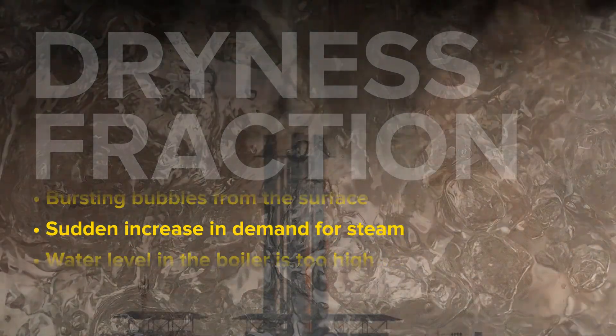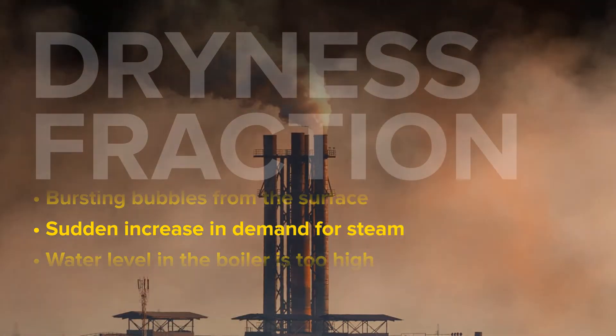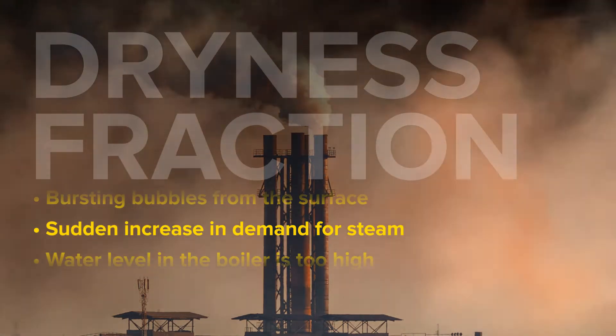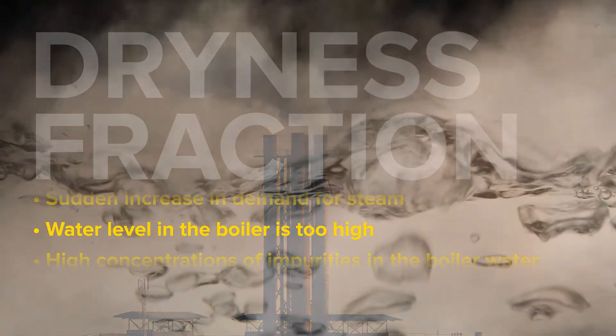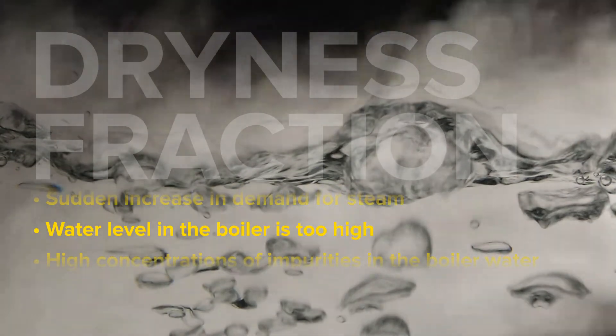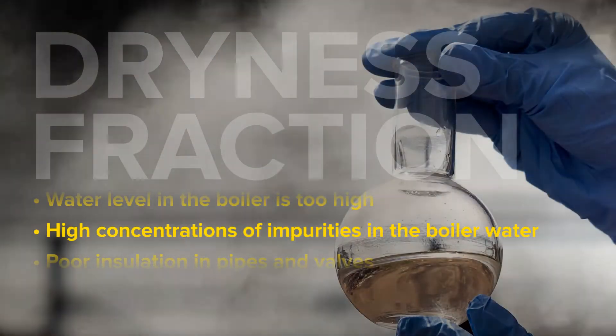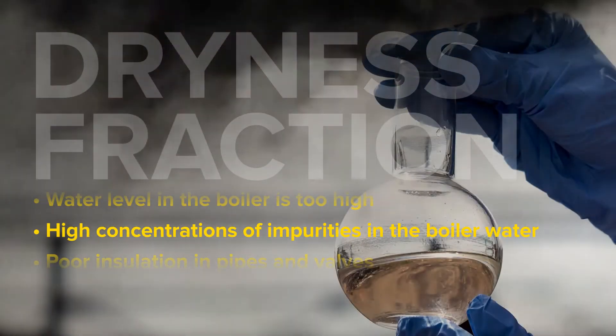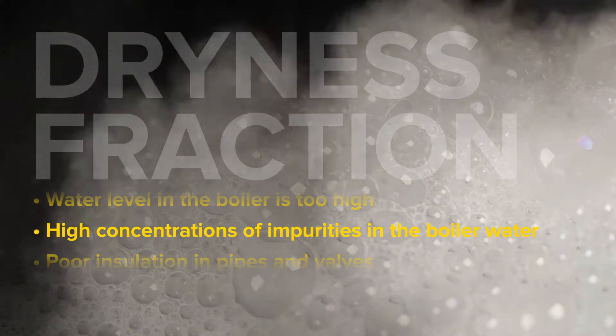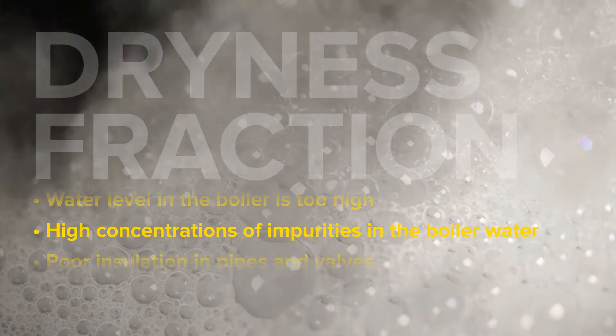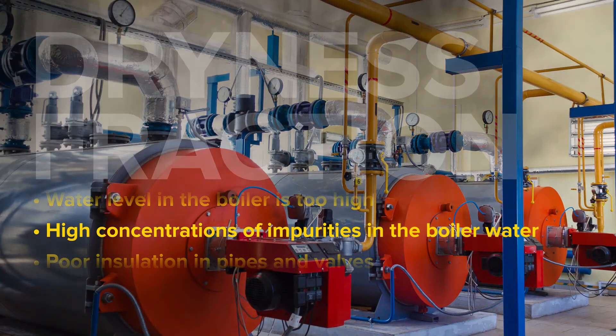Or, if there is a sudden increase in demand for steam, that reduces pressure above the water, lowering the boiling point and increasing the violence of bubbling. This is sometimes called priming or carryover. Other forms of carryover include water in the system because the water level in the boiler is too high, or high concentrations of impurities in the boiler water that reduce the surface tension and increase agitation of the water's surface. Impurities can also cause the formation of a stable foam above the water's surface, causing slugs of water to be intermittently discharged from the boiler along with the steam.